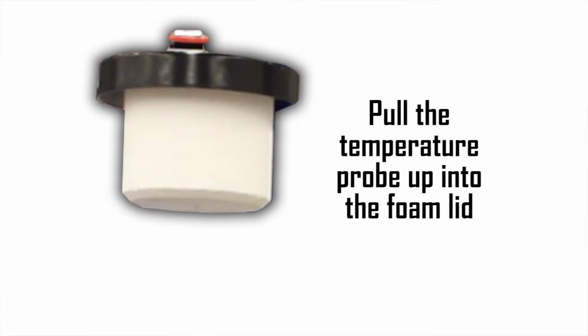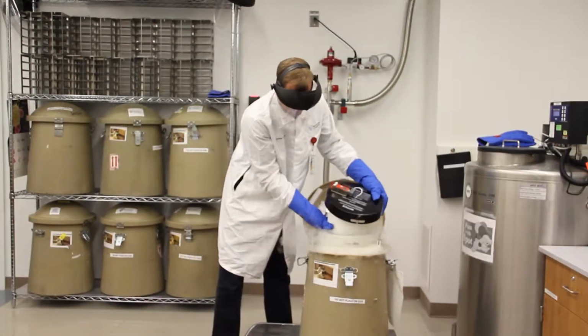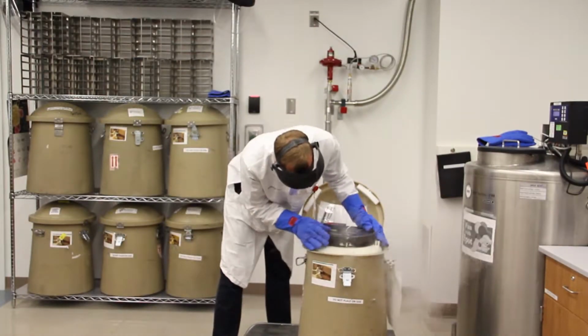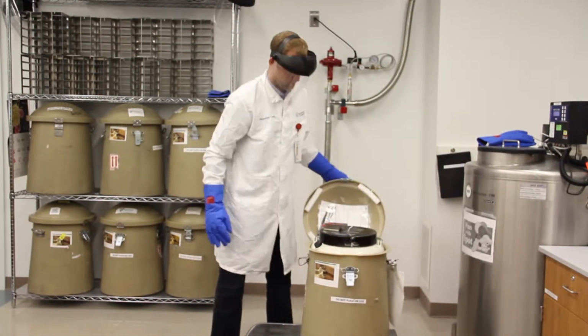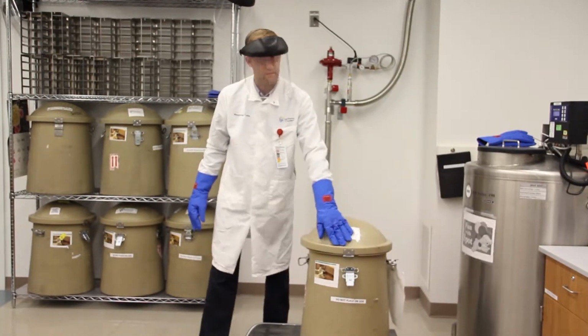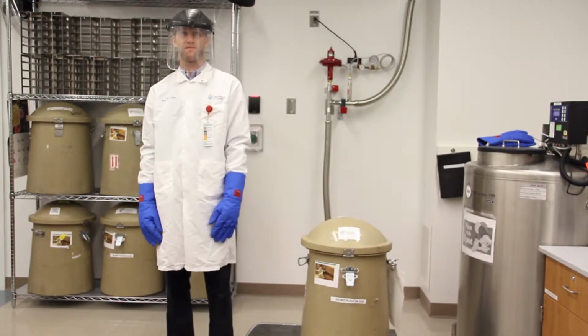Before replacing the black dewar lid, pull the temperature probe into the foam lid as demonstrated. Then replace the black dewar lid and close the cryoport hood. Please note that the temperature probe should never be in contact with the liquid nitrogen.